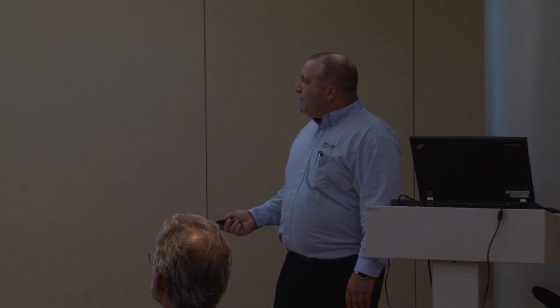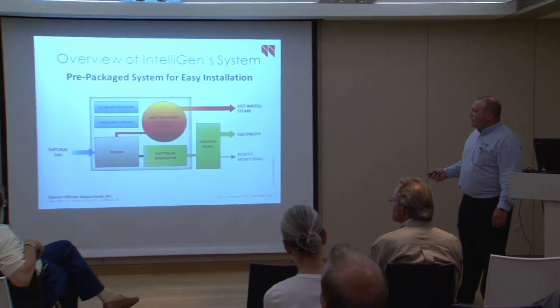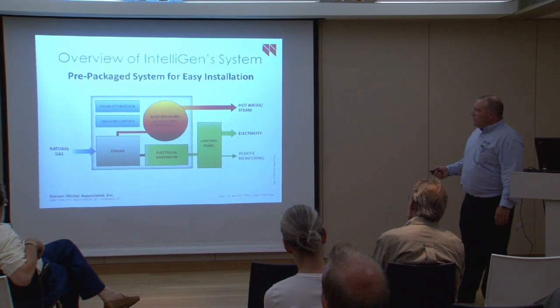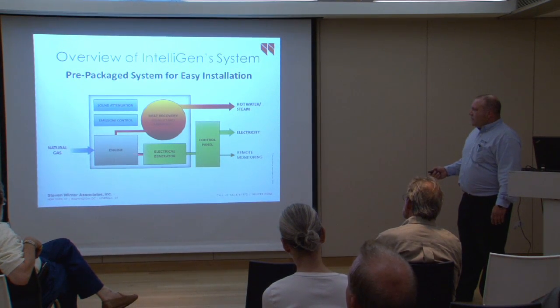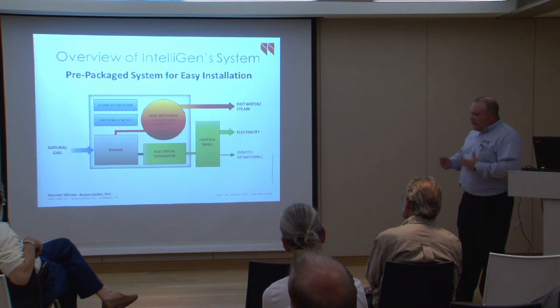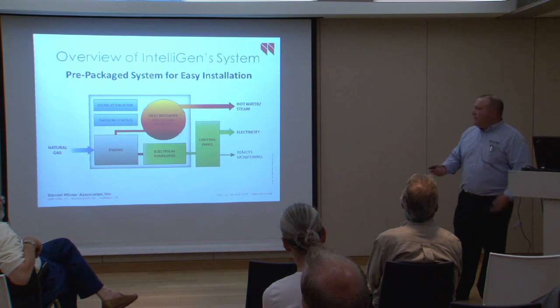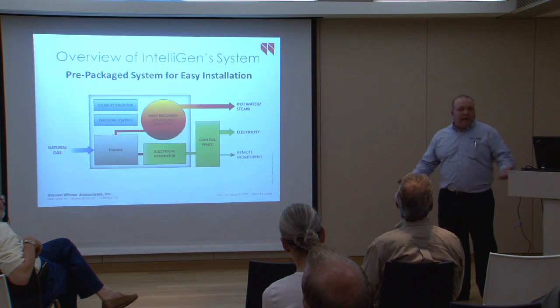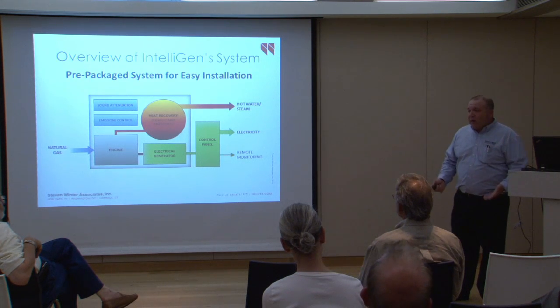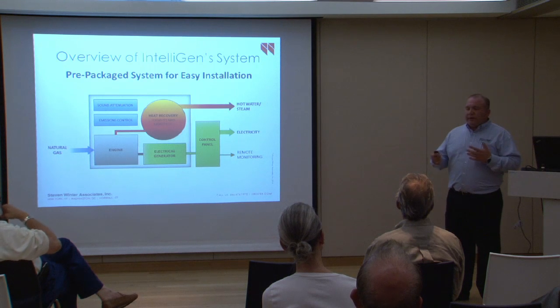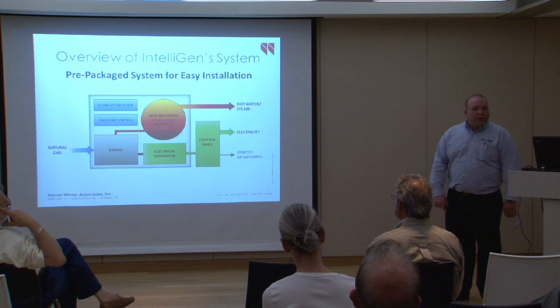So what is cogeneration? Basically, we're taking natural gas and converting it to make heating and/or cooling and electricity. One power source gives you two outputs, hence the term cogeneration. Our systems are comprised of a reciprocating engine and a generator inside the box, with heat recovery also in the box. The engine burns natural gas and generates electricity as one output, and the heat from the engine is captured and transferred to the building. We can make steam and hot water with that heat. In most cases we're always making domestic hot water for a building, and in many cases we can do heating in the wintertime and cooling through absorption chillers.